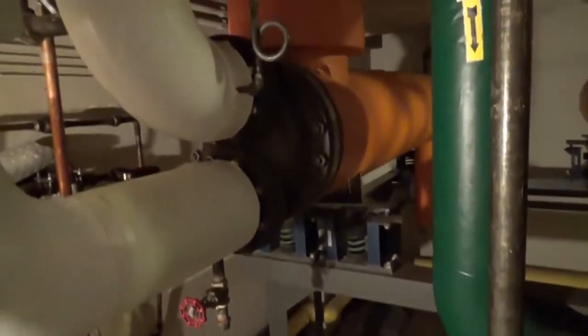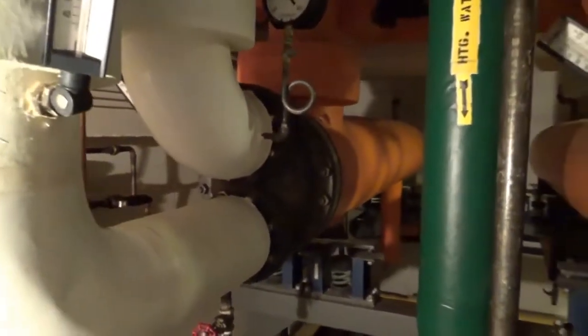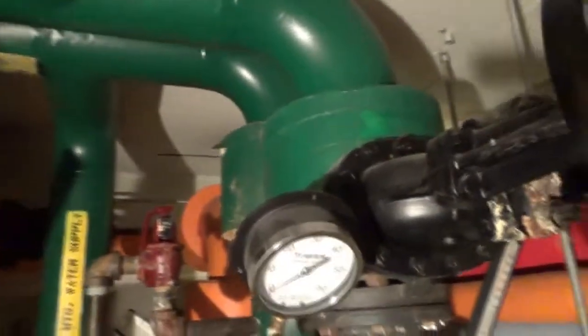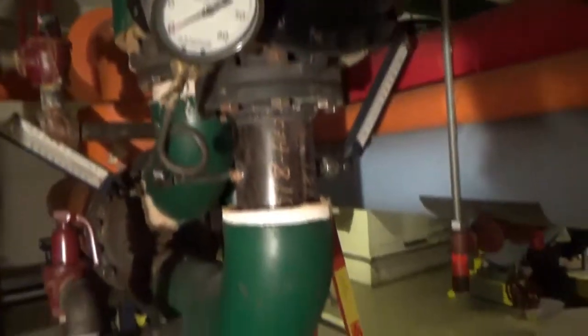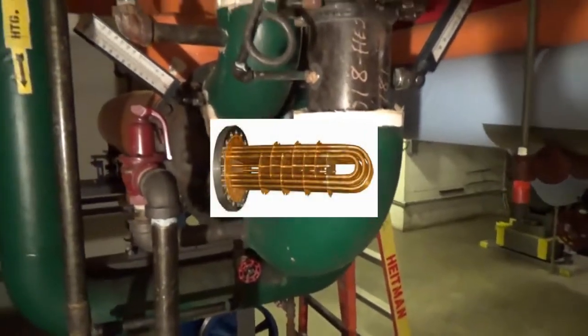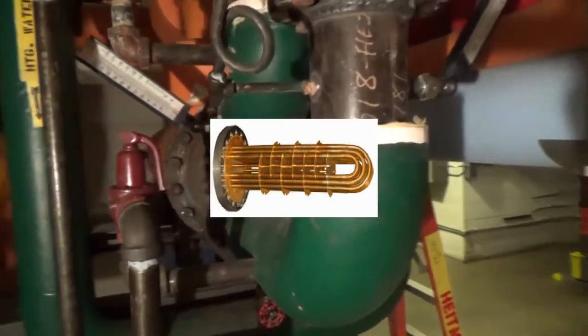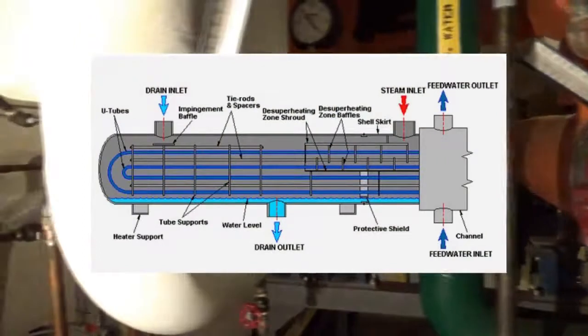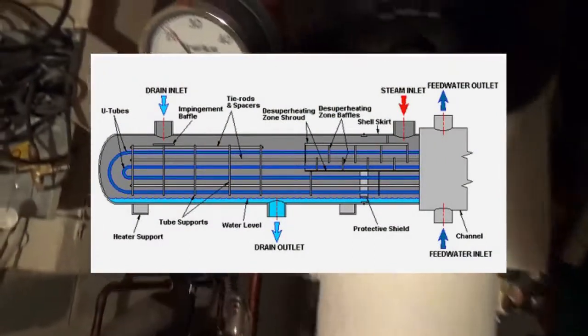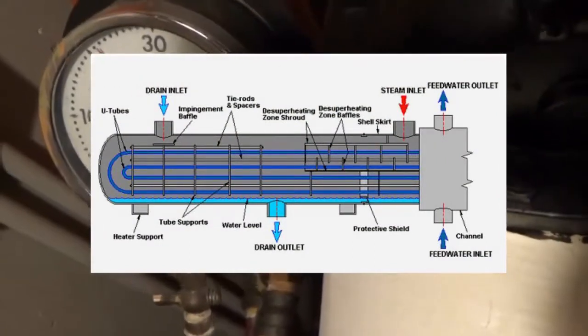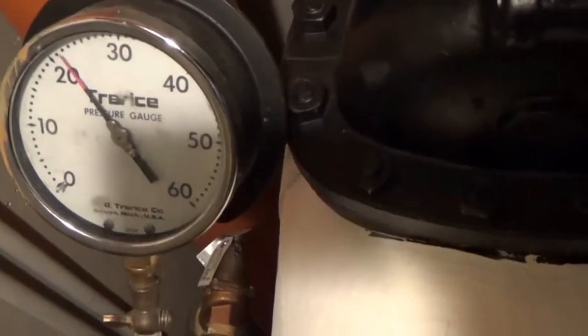Over here on the side we have two heat exchangers. This is the main heat for the building. What we have is a bundle pack that slips inside of those orange tubes way in the back. The water runs through that bundle pack, and around that bundle pack is steam. That steam is what warms that water.